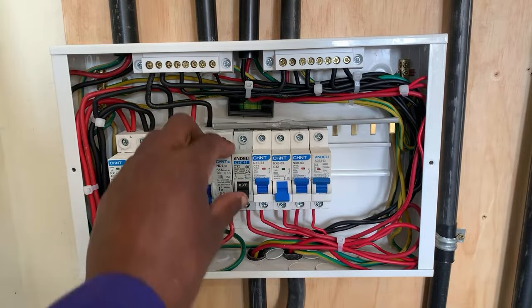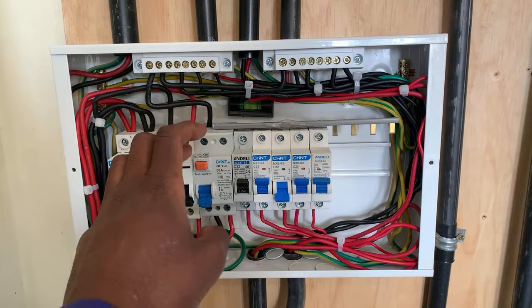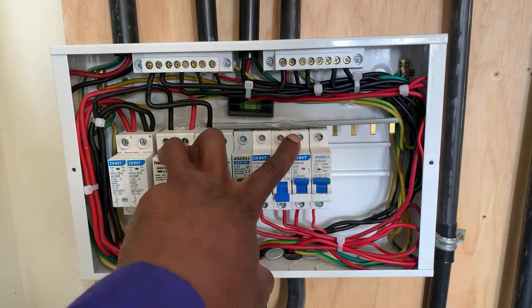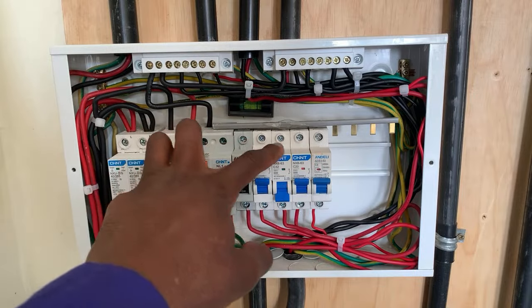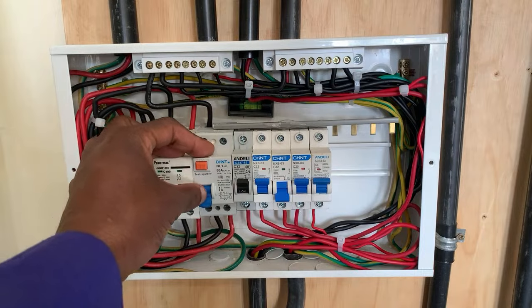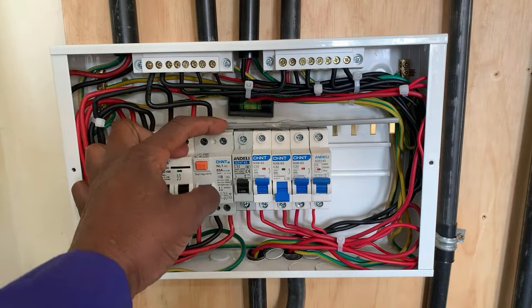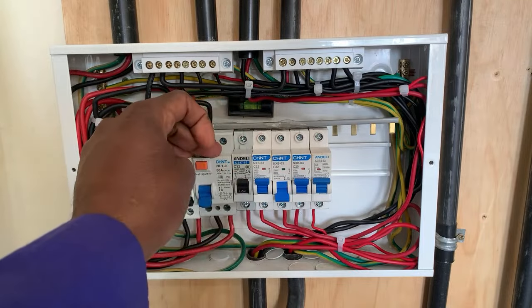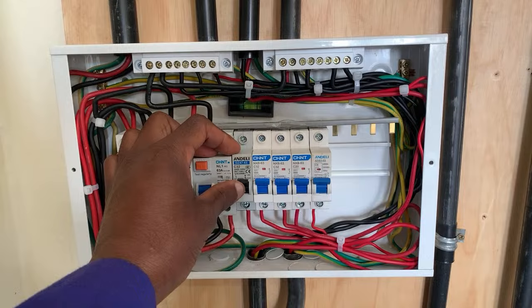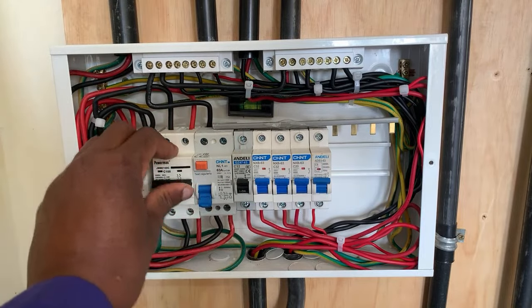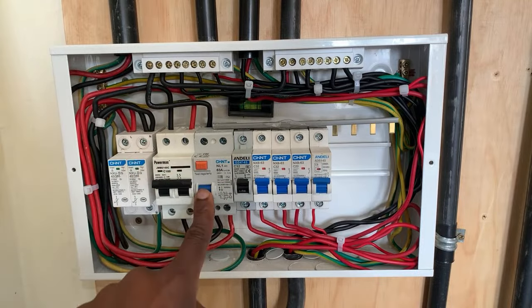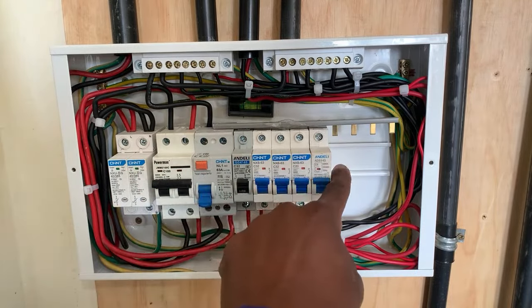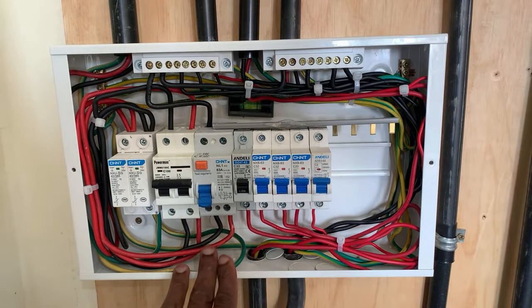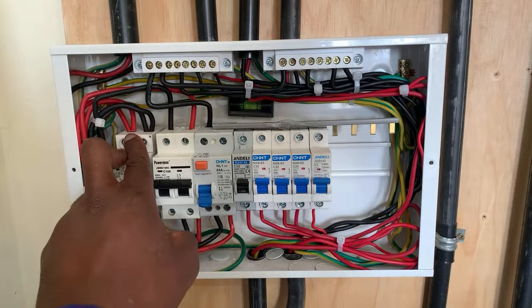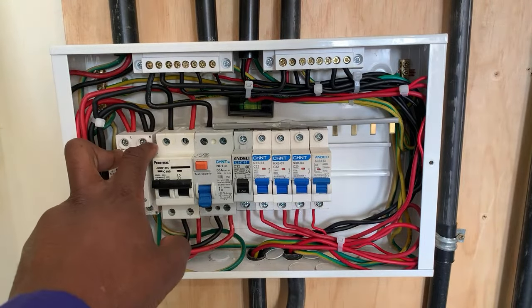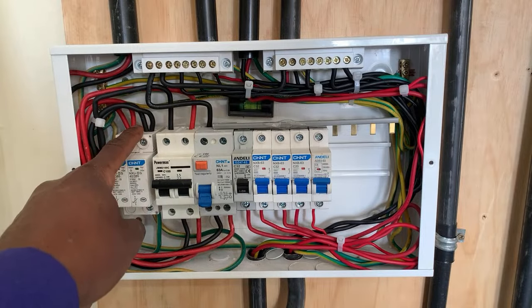Once it trips, according to how I have wired it, supply to these MCBs, which means supply to these circuit breakers, will definitely be shut down. Meaning these MCBs will not receive any supply, much as all of them might be on. As long as the RCCB is off, these MCBs will not have a power output. Because as you can see, the way I've wired here, we have looped the phase and the neutral.